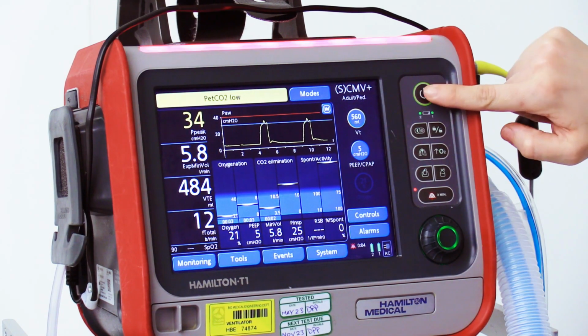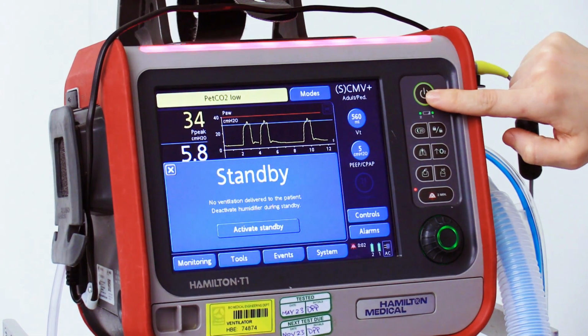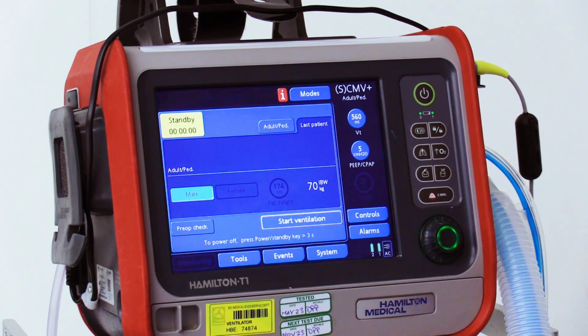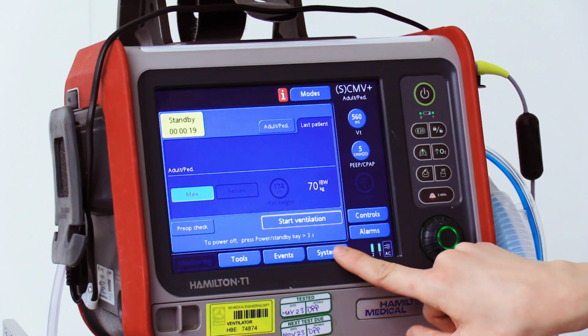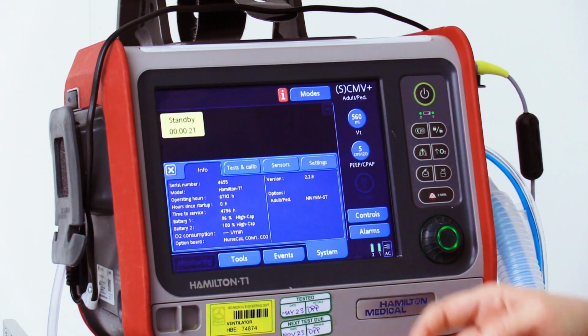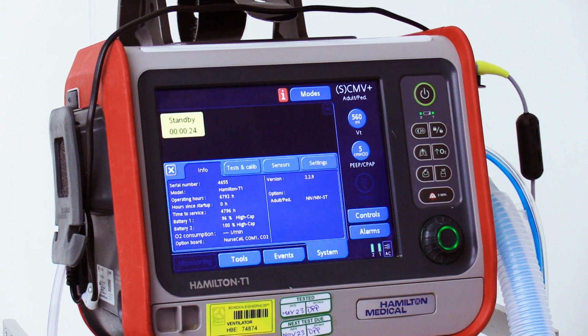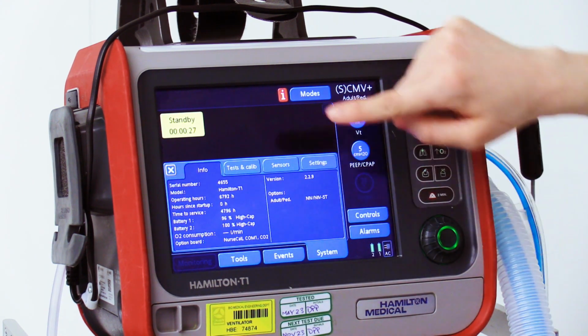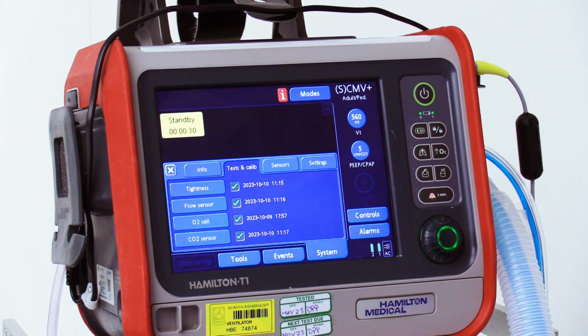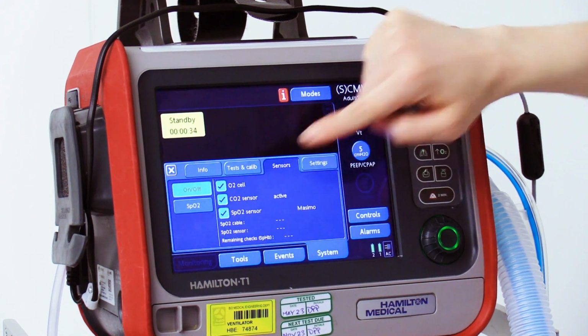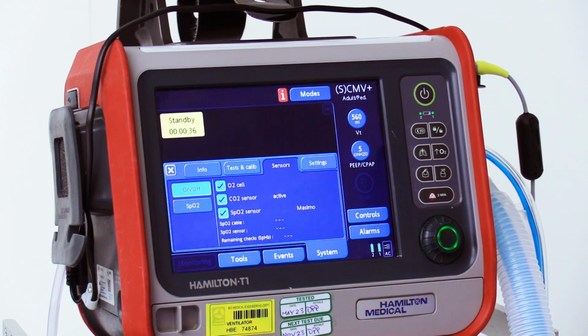To stop ventilation and enter the standby mode, just press the Power Standby key, then touch the Activate Standby button. Now this is the System tab where we can find various ventilator information. In this window there is the tests and calibrations that we performed already.